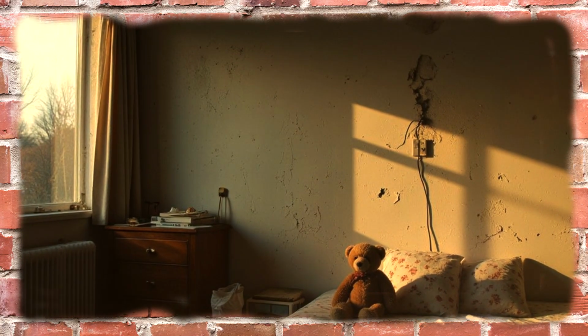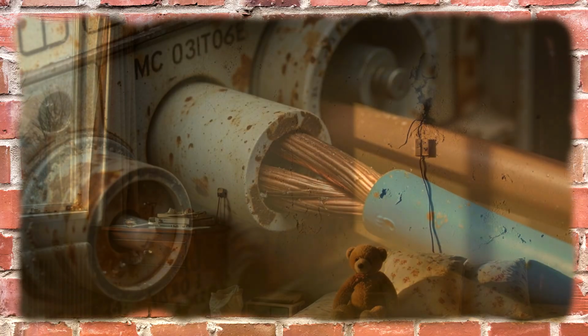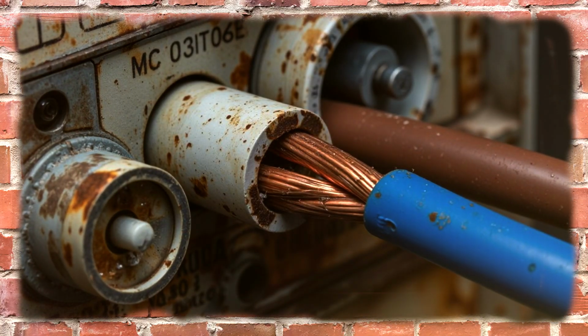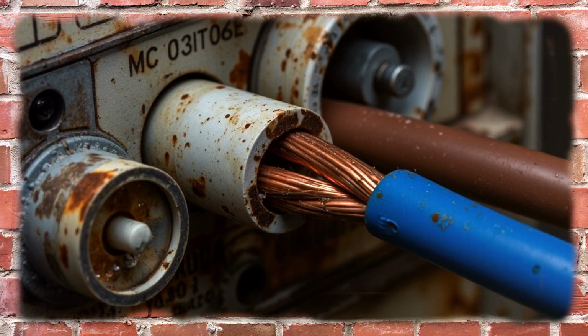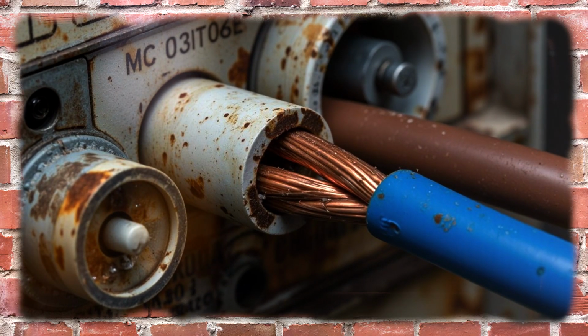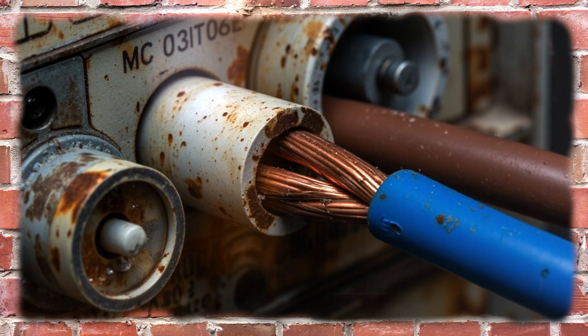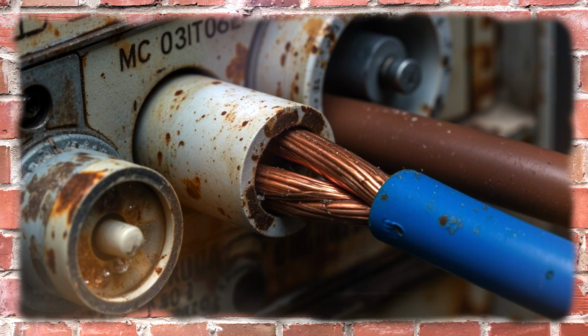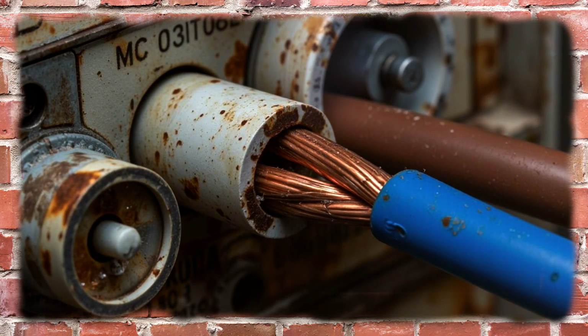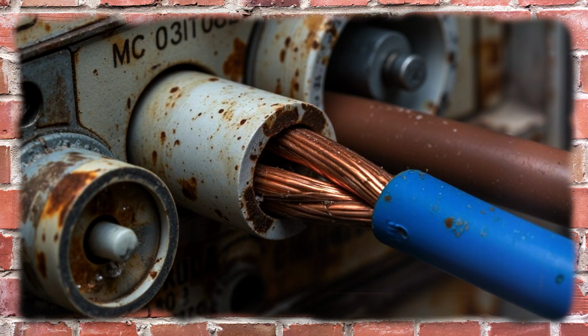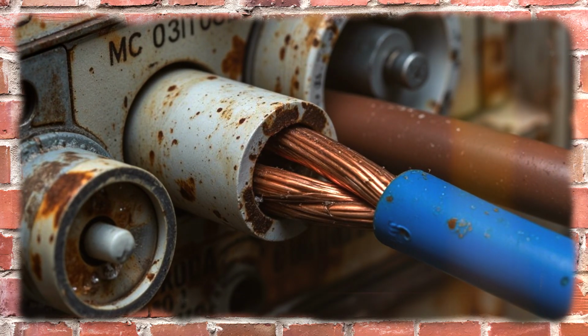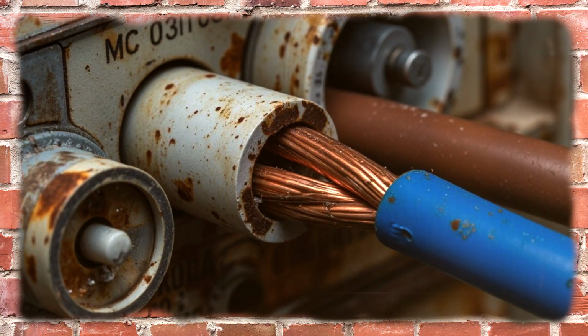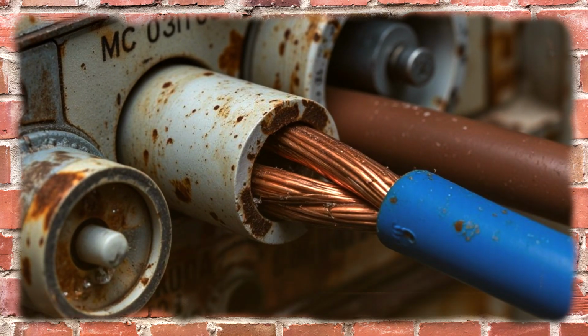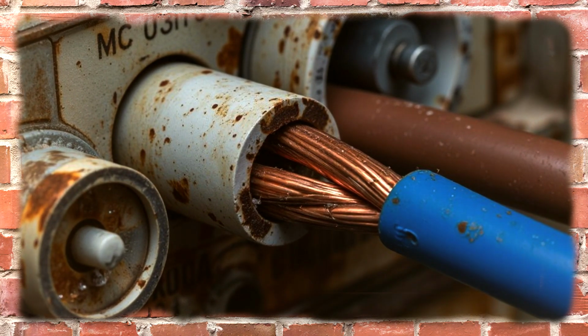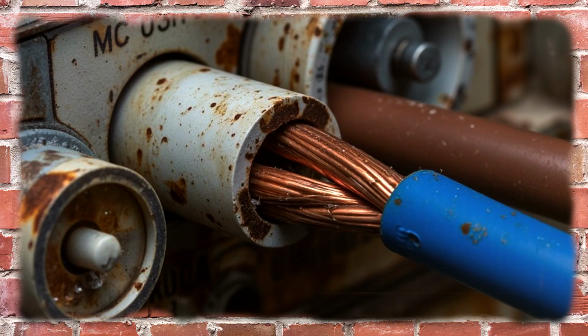This architectural difference directly affects conductor sizing. For the same appliance power, current in a US circuit will be roughly double that in a European one, meaning thicker wires are needed in the US to deliver equivalent power. Hence the standard 12 AWG, American wire gauge, size for US outlet circuits, equivalent to about 3.3 mm squared, versus the common 2.5 mm squared used in Europe and Russia for the same purpose.